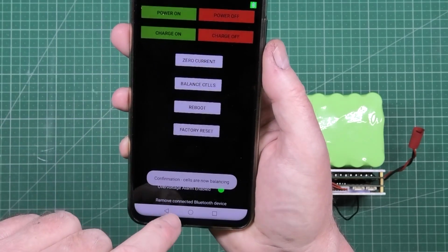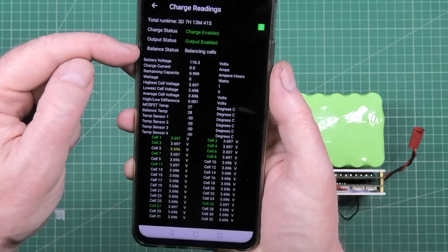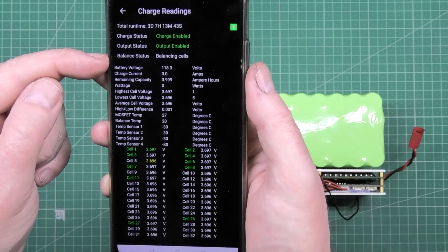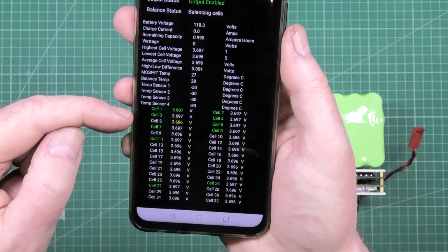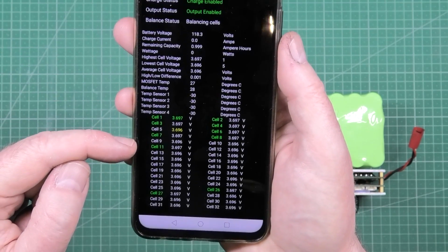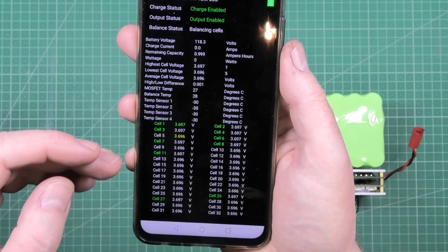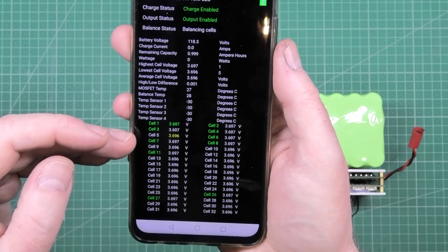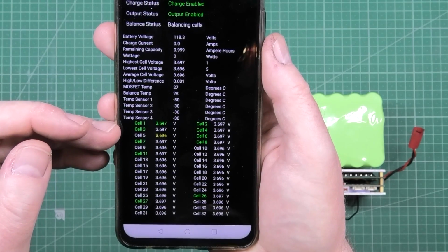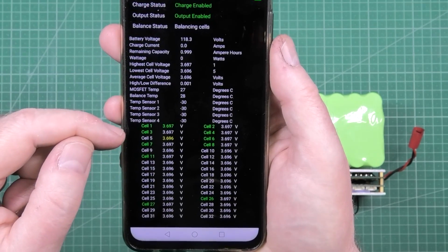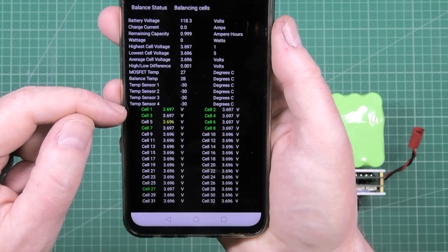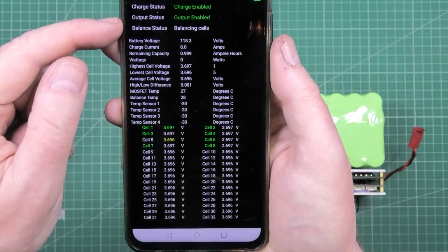Balance cells: you can manually force a balance, as in this is balancing there. That's all related to the settings screen, which has a minimum cell balance voltage you put in. So if that was set to 3.7 volts, this wouldn't start balancing.